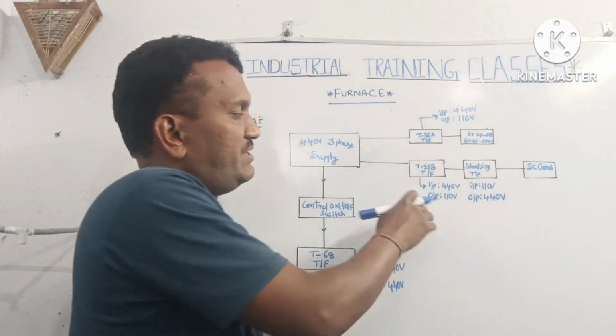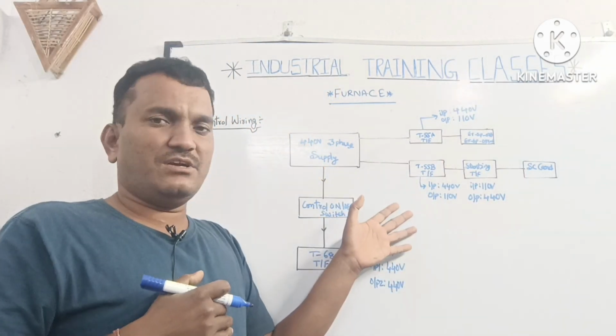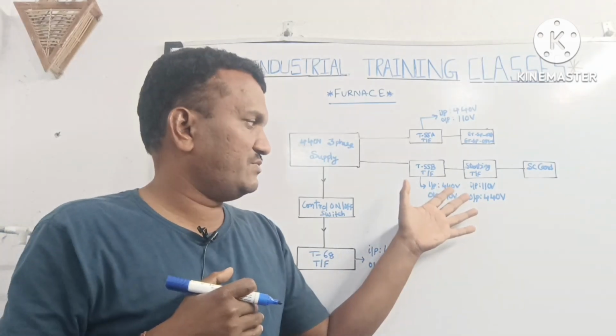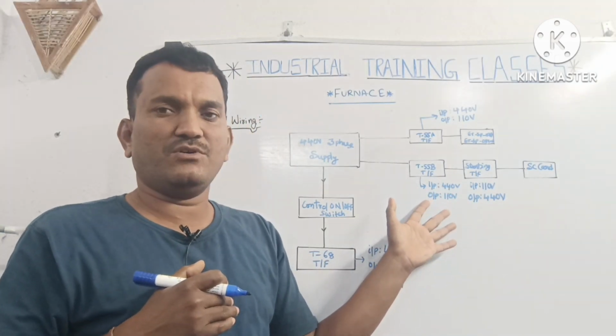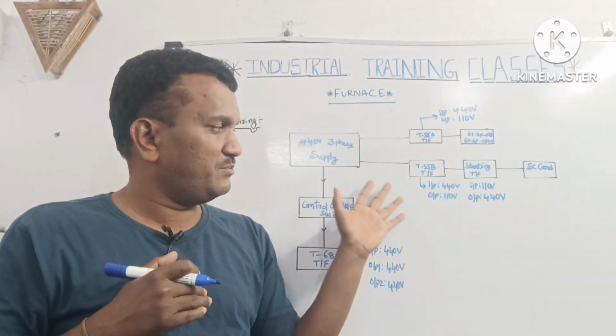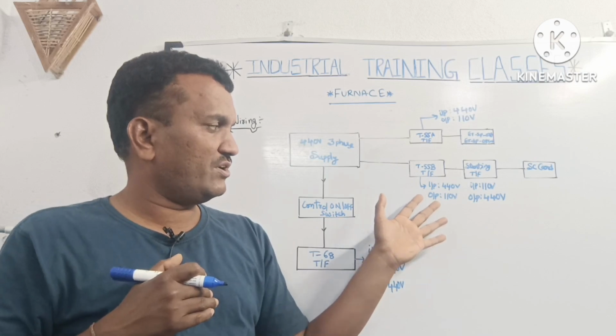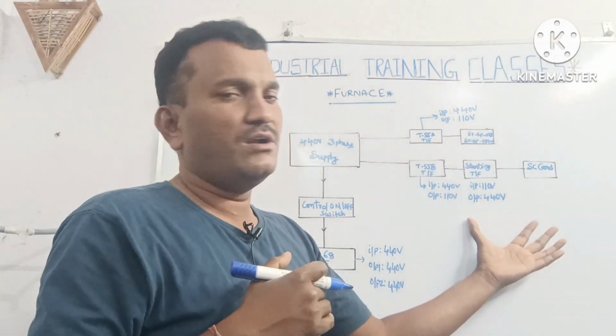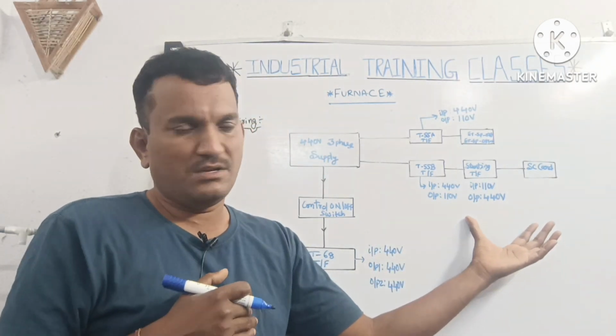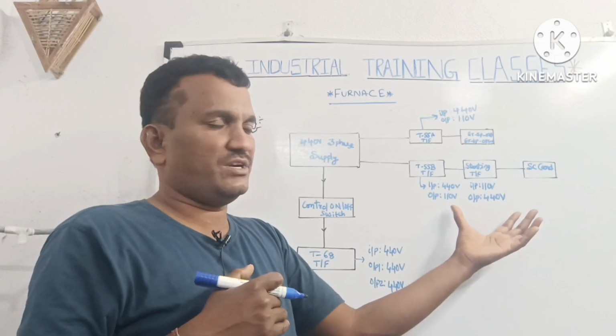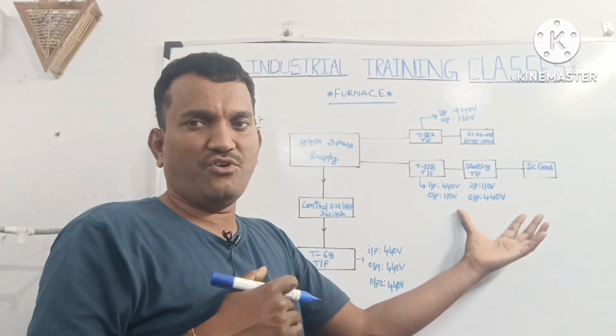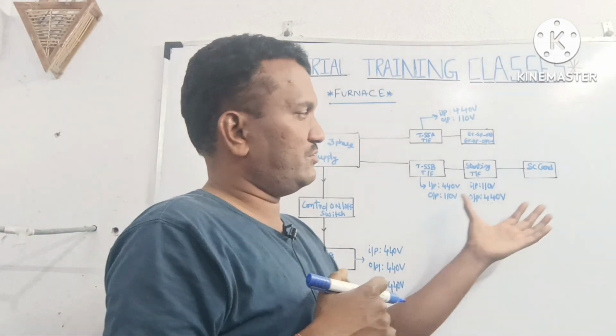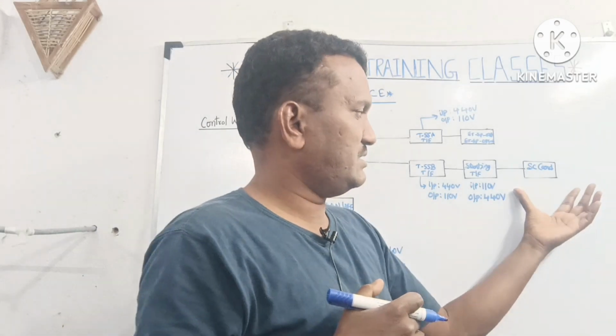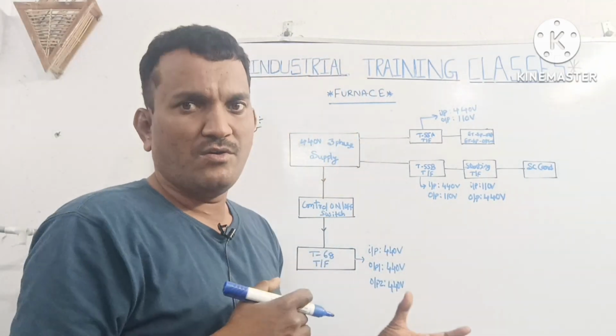Next, the T55B transformer - input is also 440, output is 110 volt. This input 440, output 110 volt goes to the starting transformer. The starting transformer input is 110 volt and output is 440 volt. Finally it goes to the SC card - SC card means starting card.